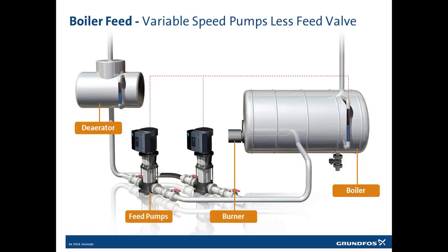Okay, Soren, this is a very interesting slide. We've got a couple of questions about this one. Number one question is, how do we control the heat around the seals on this type? So when we have speed control pumps, I'm thinking the question is, how do we avoid seals heating up due to lack of lubrication when we are using frequency control and there's no bypass?